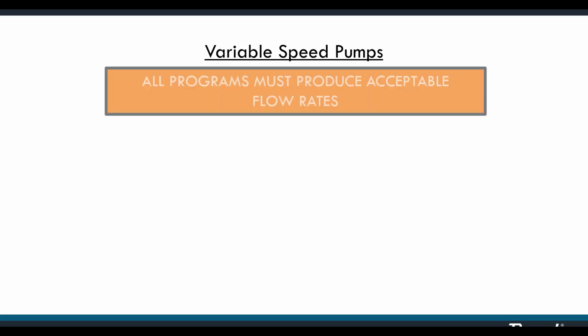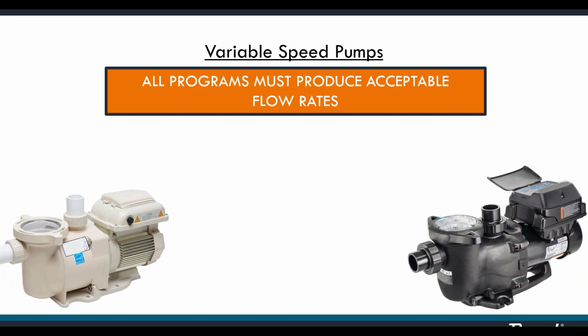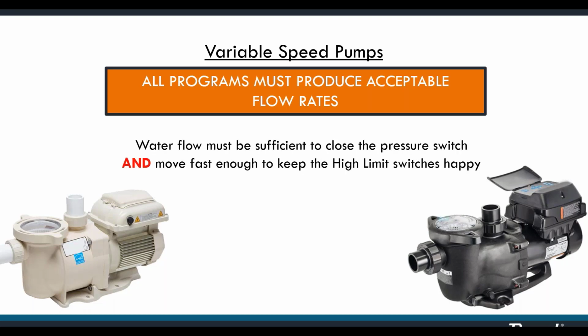There are many factors that can influence rate of flow, but the pump is the most important. If you're working with a variable speed pump, flow rates can be adjusted from there. Just make sure that all programs fall within acceptable flow rates. Bear in mind that at the lower end of the parameters, you might find a flow point at which the heater pressure switch will still close, but there's not quite enough water running through the exchanger to cool the tubes sufficiently. So then the high limit switches get tripped and shut the heater down.